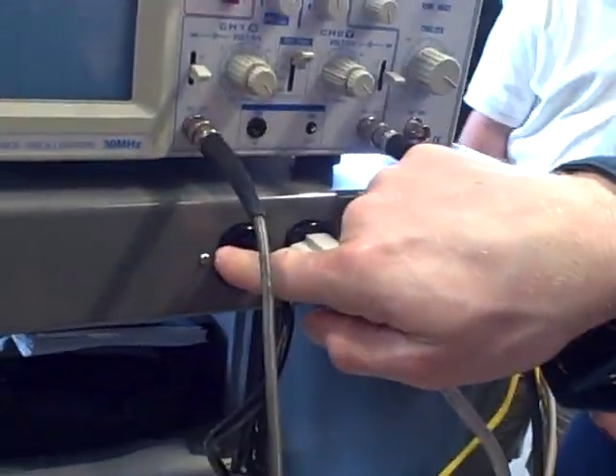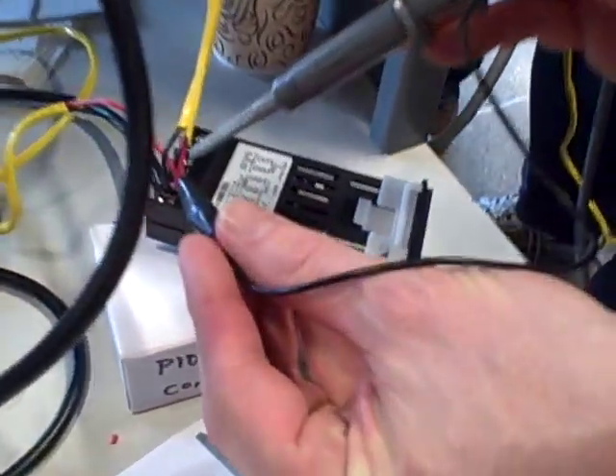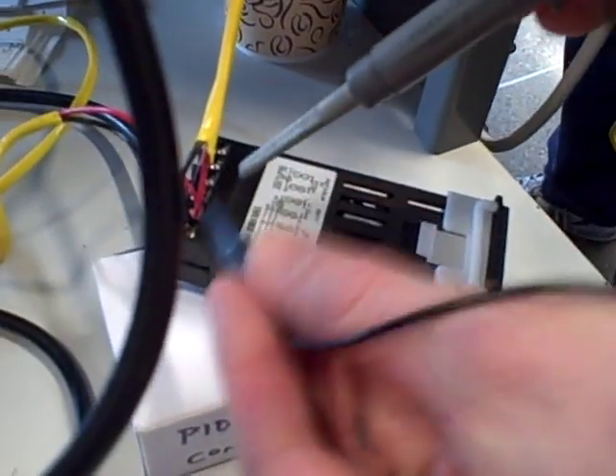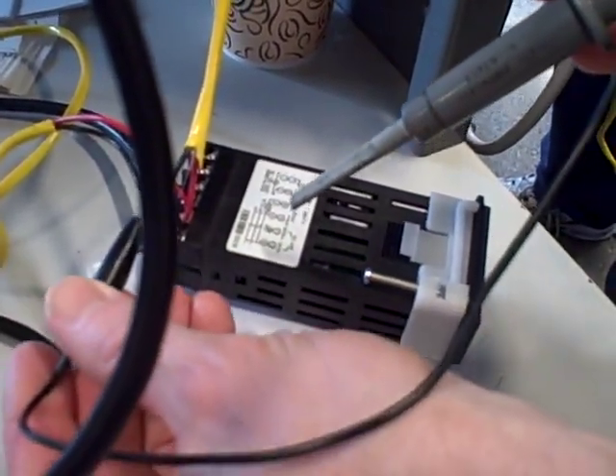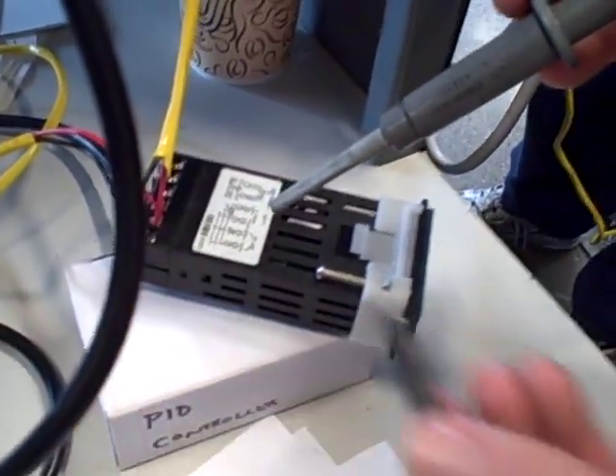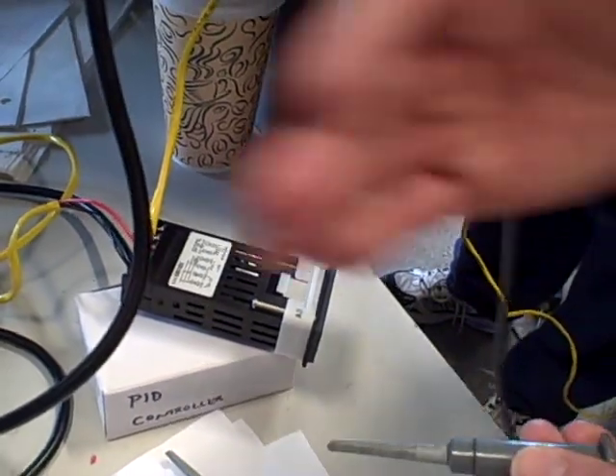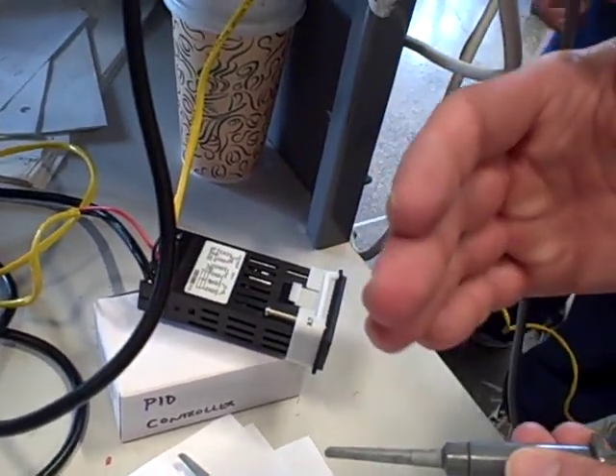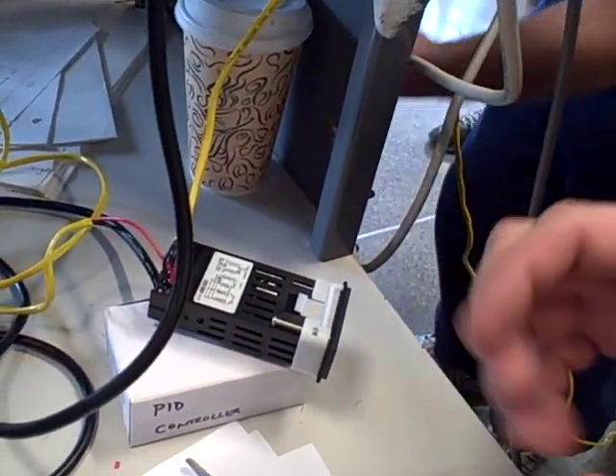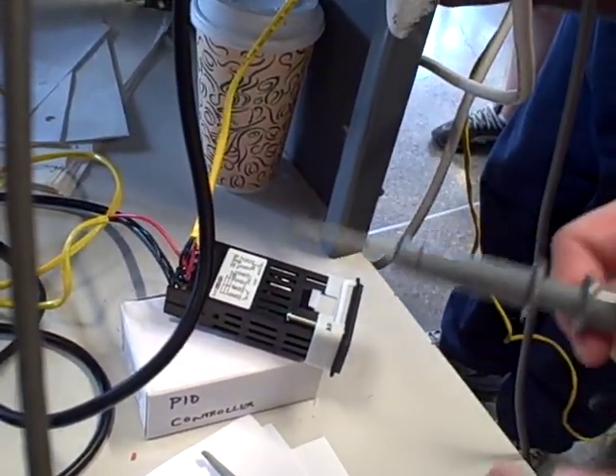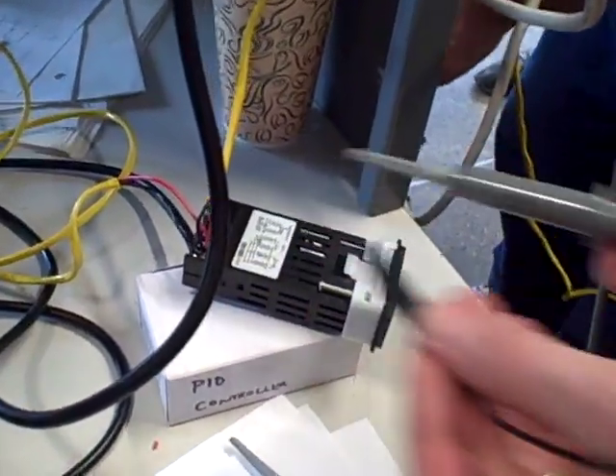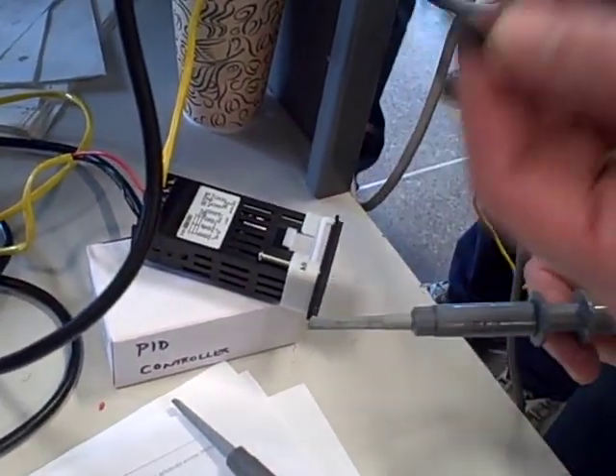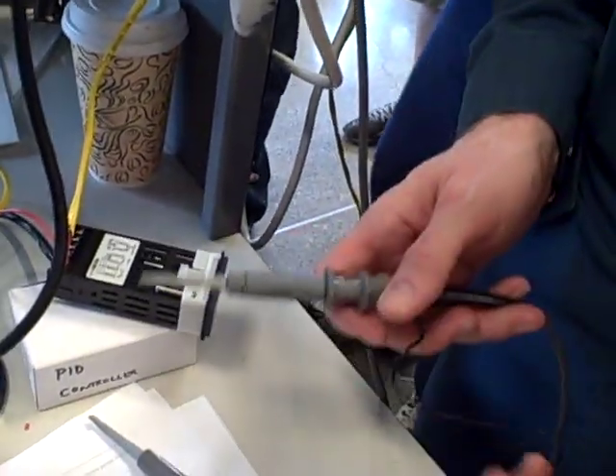That's going to be a problem for us because if I make a connection right across my RS-485 communications with probe and ground, I'm going to be forcing one line of that to be a ground potential. That could easily cause signal reflection problems and other errors that we really don't want to have. So I want to be able to measure the voltage across there without forcing one of those terminals to go to ground potential. That's our problem.